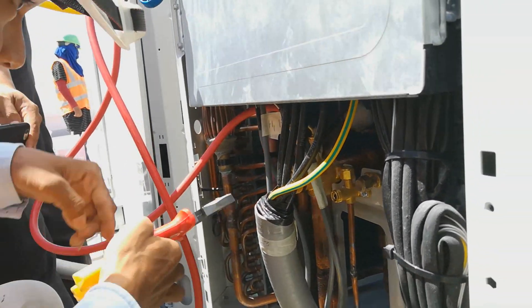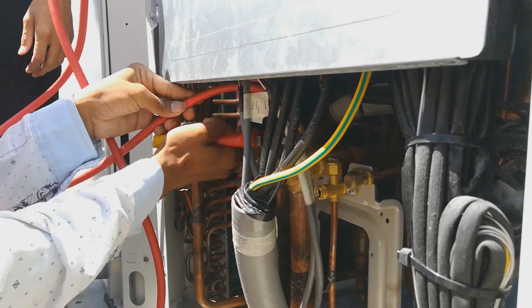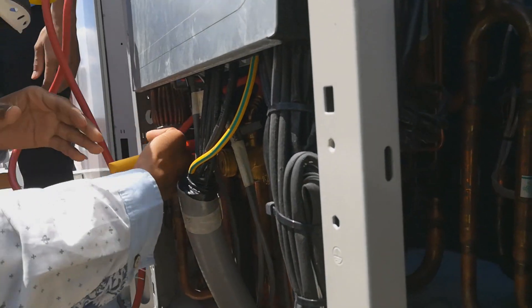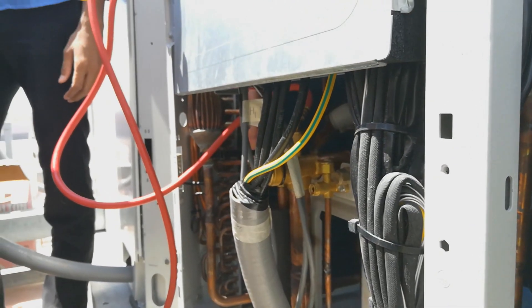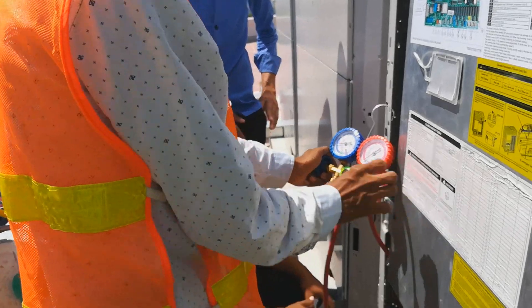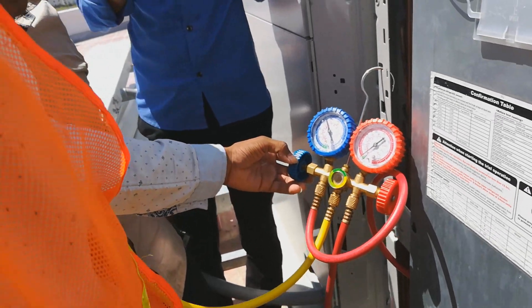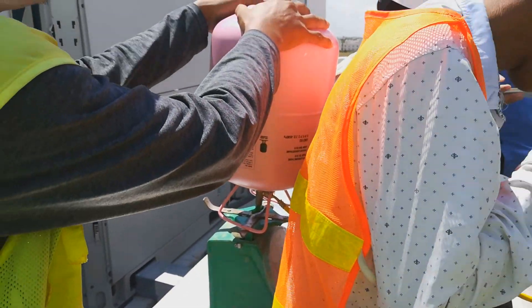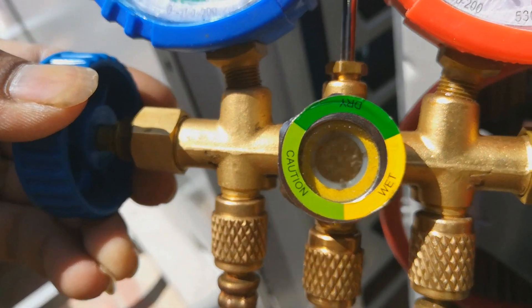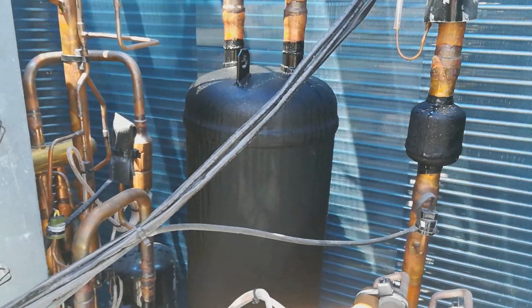The pipe is connected to the low pressure pipe section to allow refrigerant to flow into the system. Now it's connected to the pressure gauge between the refrigerant tank and the system. They open the pressure gauge valve to add the refrigerant. For this method, we put the refrigerant tank upside down to get liquid refrigerant into the system through the suction pipe of the compressor.